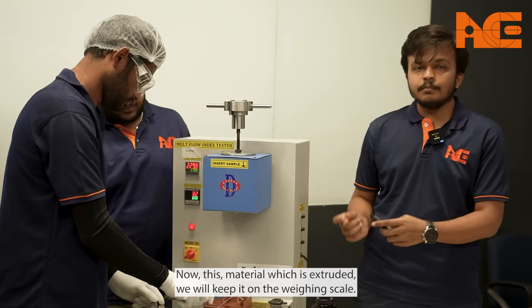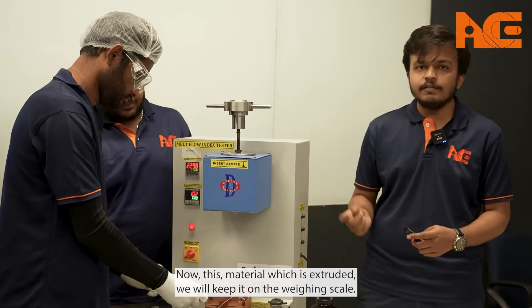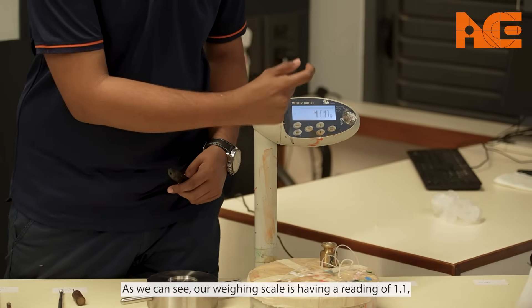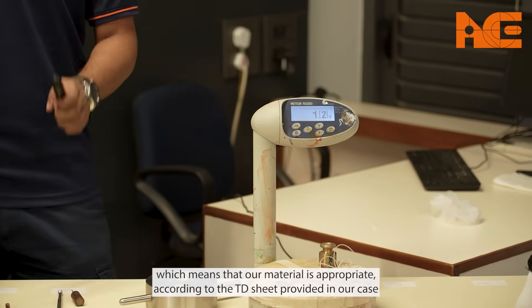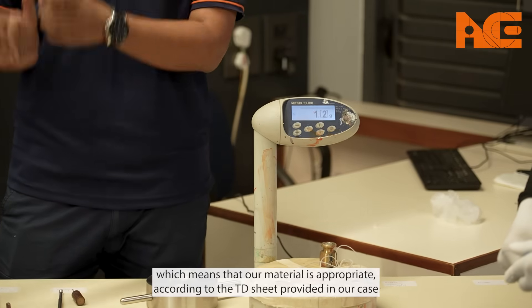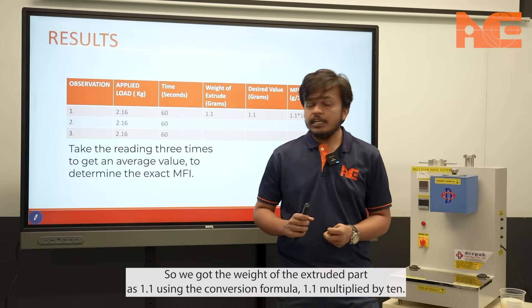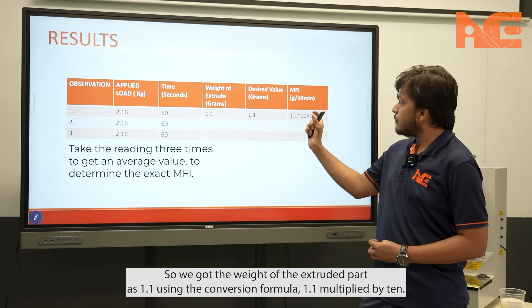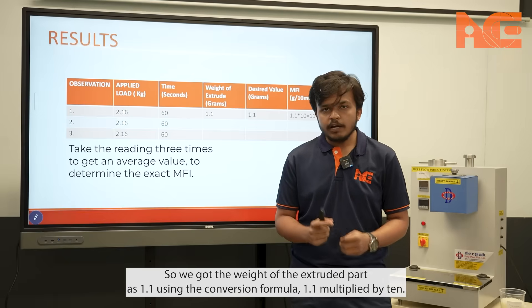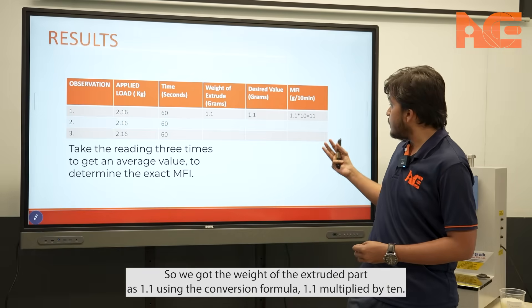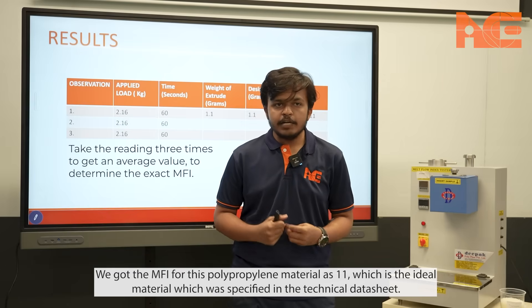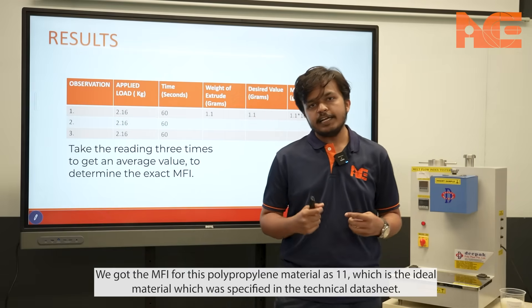The extruded material is placed on the weighing scale. As we can see, our weighing scale reads 1.1 grams, which means our material is appropriate according to the technical data sheet. Using the conversion formula — 1.1 multiplied by 10 — we get the MFI for this polypropylene material as 11, which matches the ideal value specified in the technical data sheet.